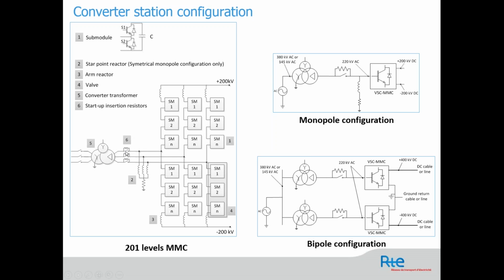So basically, what happens is that during the startup, the switch here is open, and the resistance will be used just to limit the inrush current and to charge the capacitor, and then at the end of the startup sequence we will switch to bypass the resistance and go to normal operation.